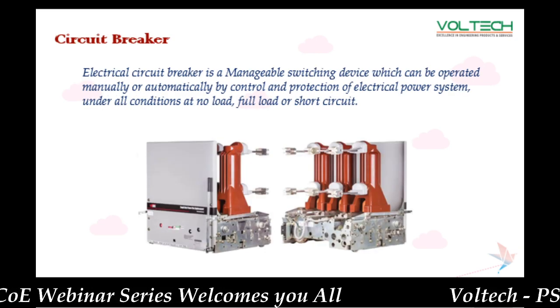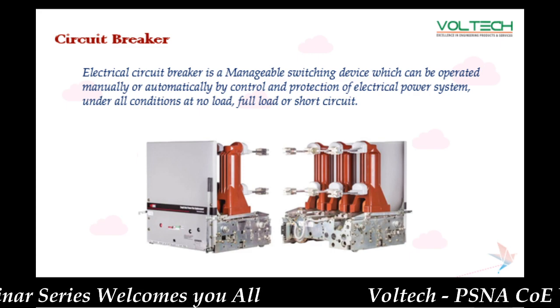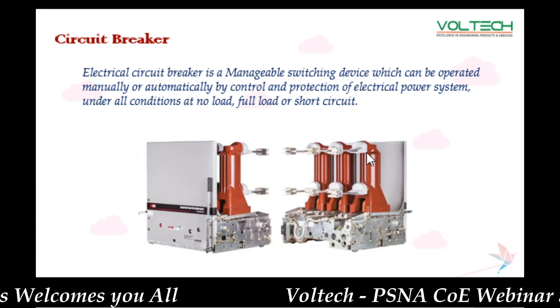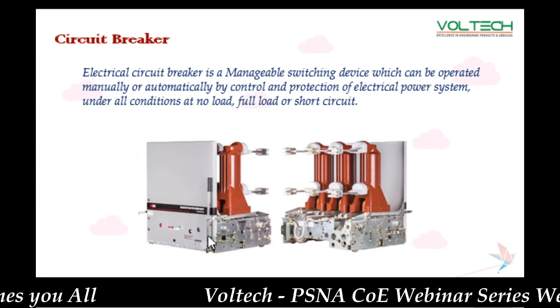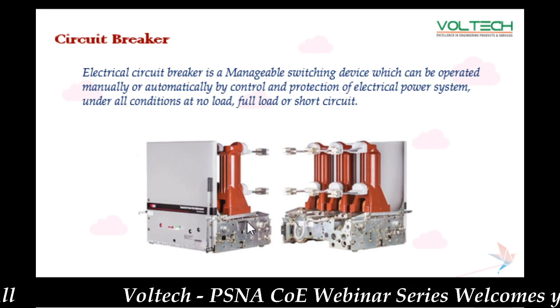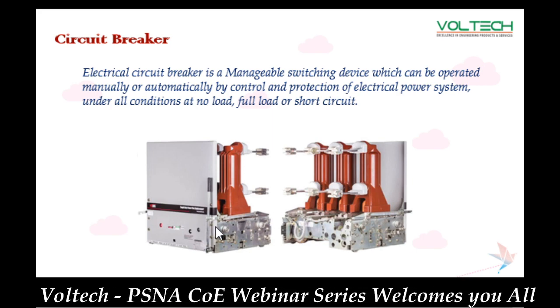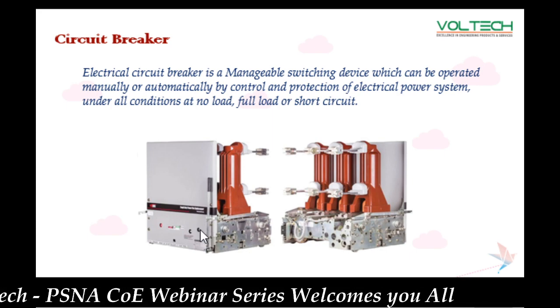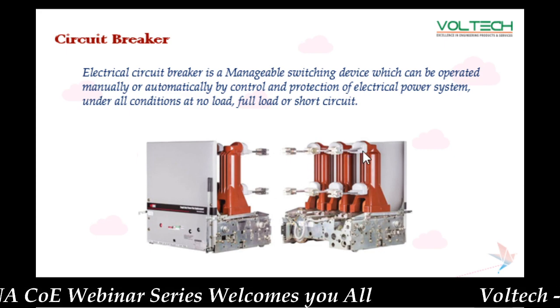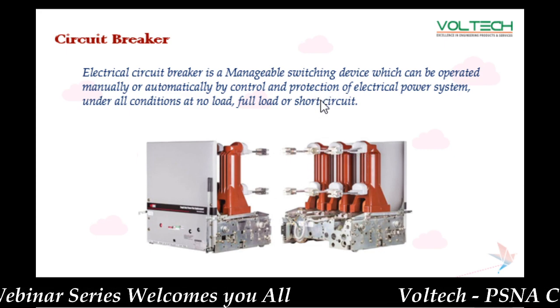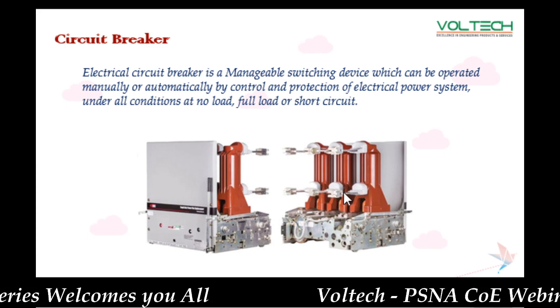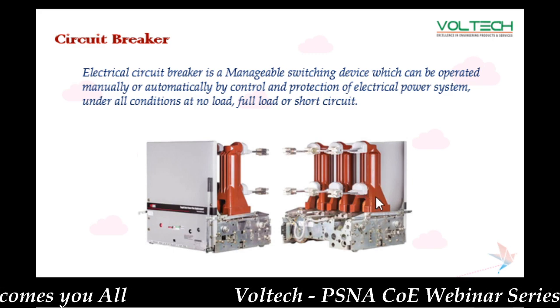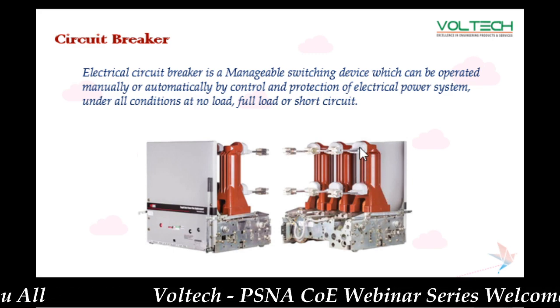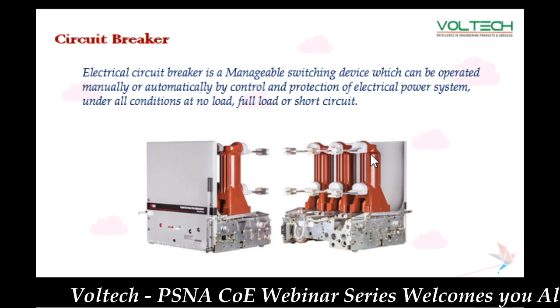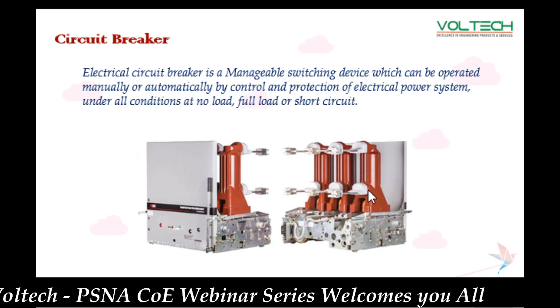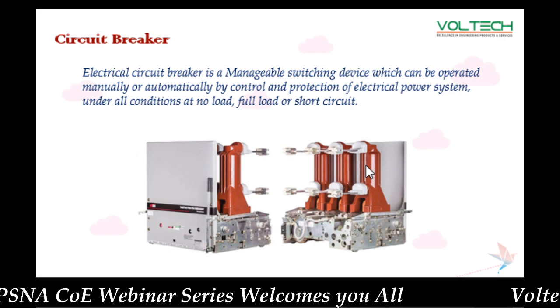So next one is the circuit breaker. This is the portion we are showing. This is the circuit breaker construction, and this is the arm. We have the circuit breaker that we can pull inside the panel. This will connect the bus bar and the cable. So this arm is going to connect with the bus bar, and this arm is going to connect with the cables. Here this is the interrupter. This is the arm, and this is the bottle or interrupter. This interrupter is vacuum, air or SF6.